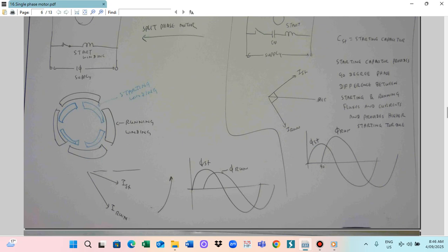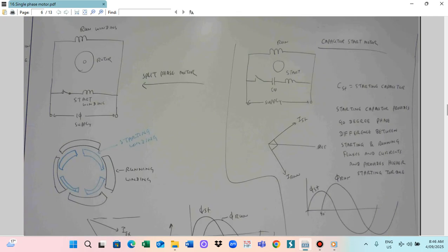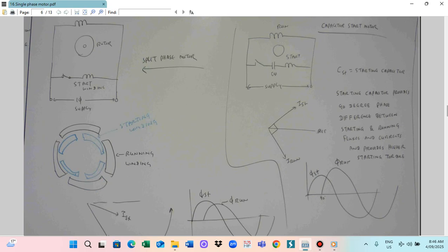So this is the way the motors are constructed. This motor is constructed so that when we want the starting current and running current to be 90 degrees apart, you have to utilize the capacitor. Normally this kind of motor we call a split phase motor, a two-phase motor. A split phase motor does not have a capacitor, but you can connect a capacitor. By connecting the capacitor, the phase will be 90 degrees. In this case, the circuit can be modified by inserting a series capacitor to the starting winding.